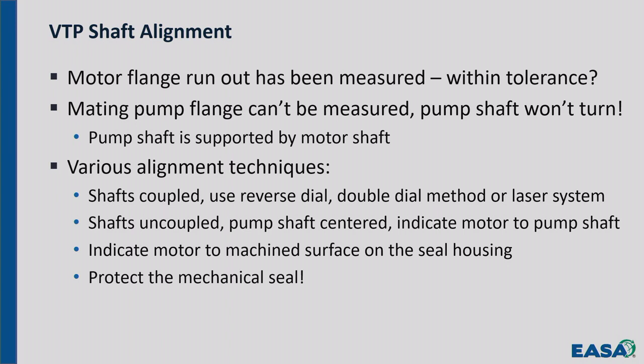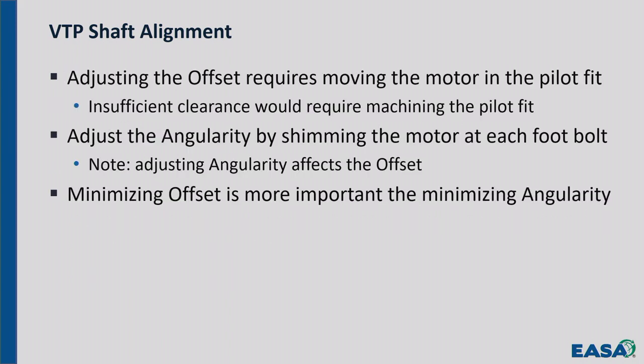Okay, protect the mechanical seal. Let's see what else is important here. If you want to adjust the offset when you're doing alignment, here's your two shafts. You want to adjust the offset, you've got to have clearance between the rabbet. If the rabbet sits solid, you can't do that. Okay? And if it's off really severely, that means sometimes you've got to go in, take the motor off, and do some machine work, or go to work with a hand file to give yourself some room to move that motor to get that horizontal alignment correct.